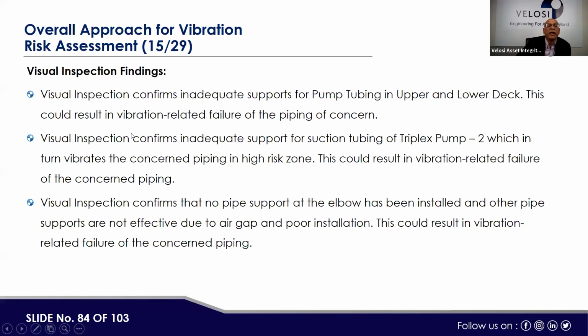Now the visual inspection findings, what we saw there. Visual inspection confirms inadequate support for pump tubing in the upper and lower deck. This could be for pump tubing, it must be maybe for lube oils. This could result in vibration-related failure of the piping of concern. Visual inspection confirms inadequate support for tubing from triplex pump 1 to triplex pump 2, which in turn vibrates the concerned piping in a high risk zone. This could result in vibration-related failure of the concerned piping.